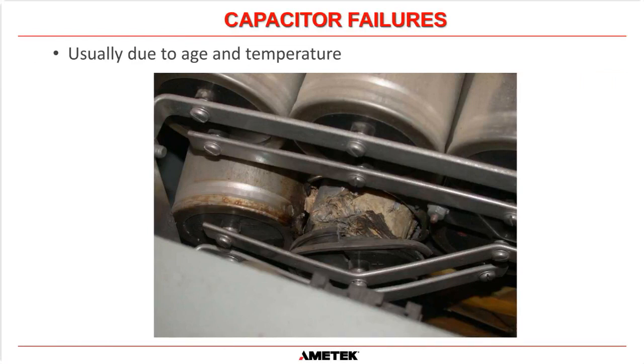The next thing that we have to take into consideration is age degradation of components inside the UPS. So the first thing that we have to look at is capacitor failures. You can see here that this is what the capacitors are supposed to look like. And this bus bar is supposed to be going straight there. And you can see that this capacitor here has ruptured, and ruptured considerably, with a certain amount of force that has bent that bus bar. We did not bend that bus bar. It was this capacitor failing that caused that bus bar to bend. And obviously, there could be some components that those bus bars get pushed into and could cause a short circuit in some circumstances. So you can see that this is not a good situation. So we want to make sure circumstances like this do not happen.